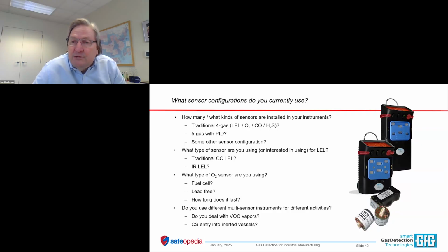Make sure, again, that you keep pace with regulatory requirements. Used to be that nobody would think about any more sensors than a two sensor design. When I got into gas detection 40-something years ago, the most sensors that could be tucked into the same instrument were an oxygen sensor and a combustible sensor, and we thought that product was amazing. And then you saw a shift to three sensor instruments that included usually H2S. And then it was four sensors that included CO as well as H2S. Nowadays, we have up to seven channels of detection built into the same instrument.